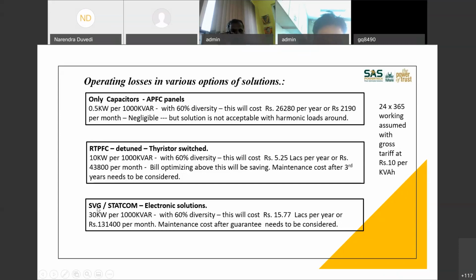Similarly, if you go for an SVG STATCOM electronic solution, the loss jumps directly from 10 kilowatt to 30 kilowatt. They talk about 97% efficiency. That means it is 3% loss. And this loss is quite obvious, because every power semiconductor sitting inside the panel will have at least 1 to 1.5 volts drop across it.